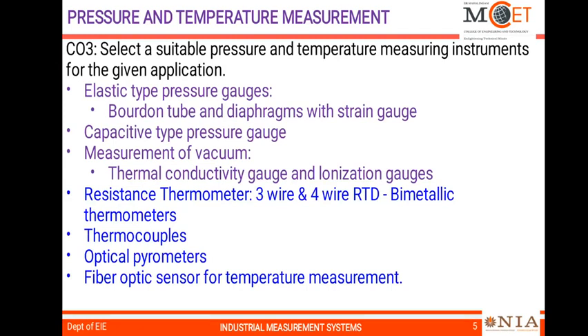CO3 deals with pressure and temperature measurement in industries. For pressure measurement, topics include Bourdon tubes and diaphragms with strain gauges — Bourdon tubes being mainly used for pressure measurement with indication only. Capacitive type pressure gauges are also covered, as most industrial pressure measurements use differential pressure transmitters based on capacitive principles. For low pressure measurement and vacuum, thermal conductivity gauges such as Pirani gauges and ionization gauges are included.